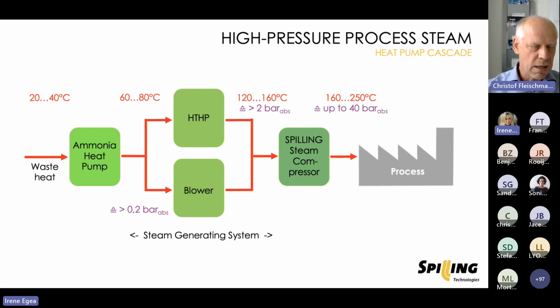The other way, what can be done to bring 60-80 degrees Celsius heat to above 100 degrees Celsius can be the way like shown below in the middle, with a series of blowers. Therefore, first water steam in the vacuum is produced, say with 0.2 bar absolute or so, and then with say 5, 6, 7 blowers or turbofans, one behind each other, this vacuum steam is compressed to overpressure level, also to 2 to 5 bar, something like this.